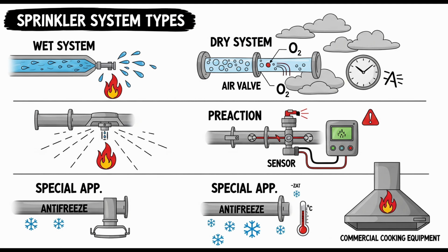Precisely. It maintains relatively stable pressure within the antifreeze system despite temperature swings. The chamber must be sized correctly based on the total volume of the antifreeze system and the expected temperature range it will experience. It must be large enough to prevent the maximum system pressure from ever exceeding the lowest pressure rating of any component in that antifreeze system loop. So the chamber size is specific to the installation, calculated based on volume and temperature delta.